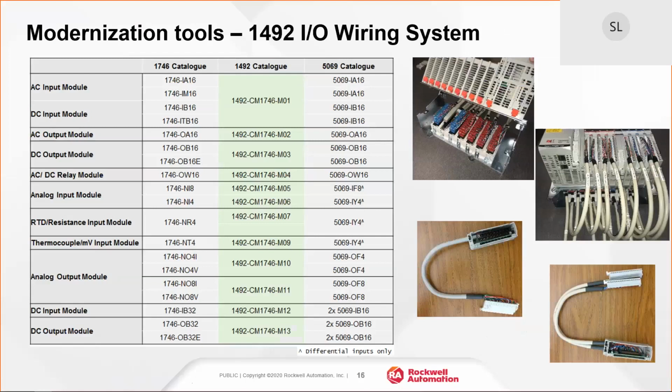And the advantage of doing it this way is that you can remove the SLC and the IOs and put this thing together within probably 10, 12 minutes, depending on the chassis size. If for some reason, after you have converted the code, it doesn't work, you can go back to the old SLC or PLC5 system within less than an hour, and your system is up and running again, so you have no risk. Sometimes, if you have all the time, probably you don't want to use this migration kit, that's fine. But as soon as you start disconnecting every single wire, going back to the original setup is going to be difficult. So again, just be sure that you have enough time to do it that way.